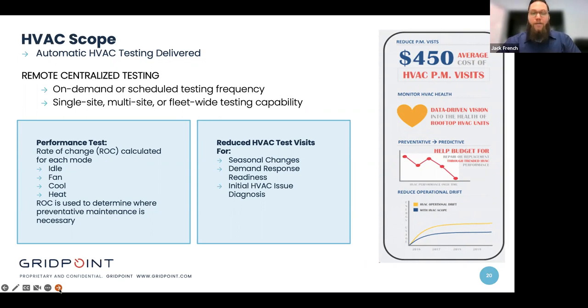But essentially, HVAC scope is automatic HVAC testing delivered. And we really like to use this tool before seasonal changes. So right now, we're nearing shoulder season, the in-between of heating season in the winter and cooling season in the summer. So now is probably a good time to start thinking about testing units in cooling mode before we enter cooling season. And then we end up in that reactive approach again, right?